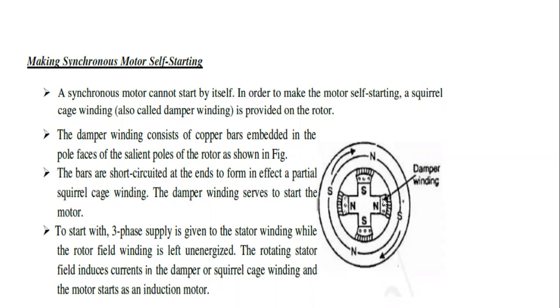By using these damper windings, the motor is converted into a self-starting motor. To start, the three-phase supply is given to the three-phase stator winding, while the rotor field winding is left unenergized.